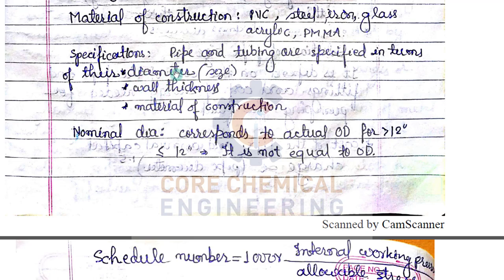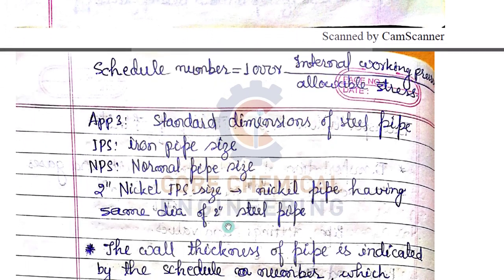Nominal diameter corresponds to actual diameter when your pipe diameter is greater than 12 inches. If the nominal diameter is less than or equal to 12 inches, it is not equal to the outer diameter. So if you are using an 8-inch or 6-inch pipe given in terms of nominal diameter, that nominal diameter will not equal the outer diameter.